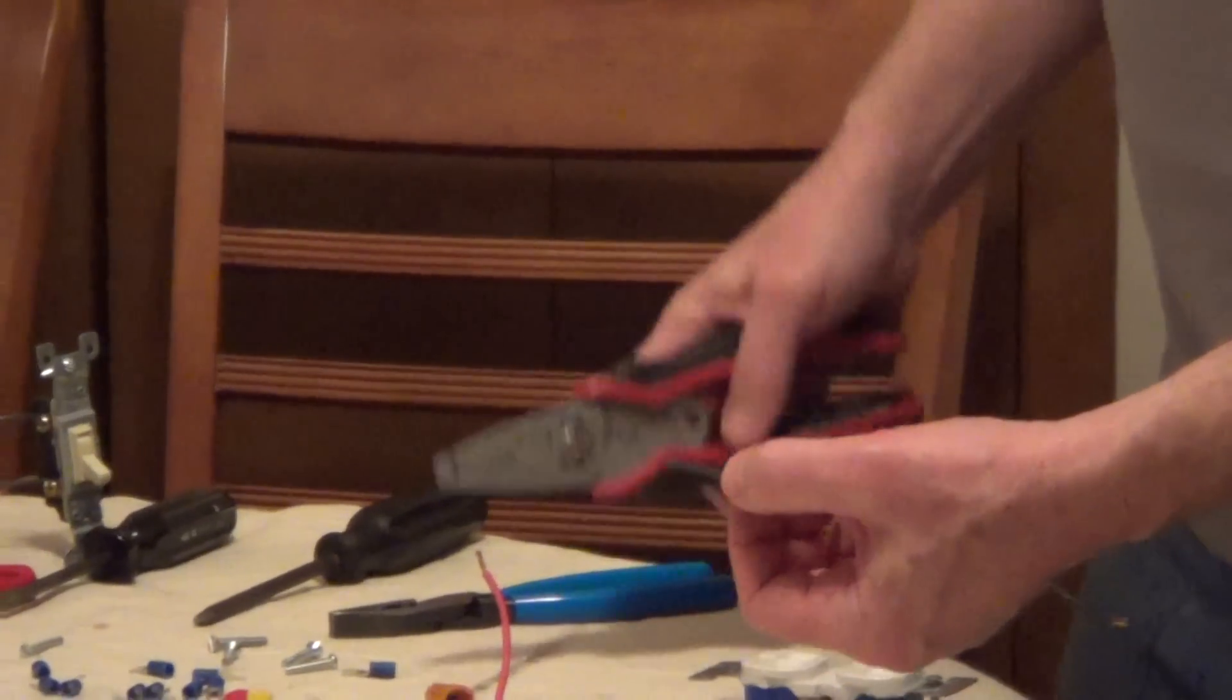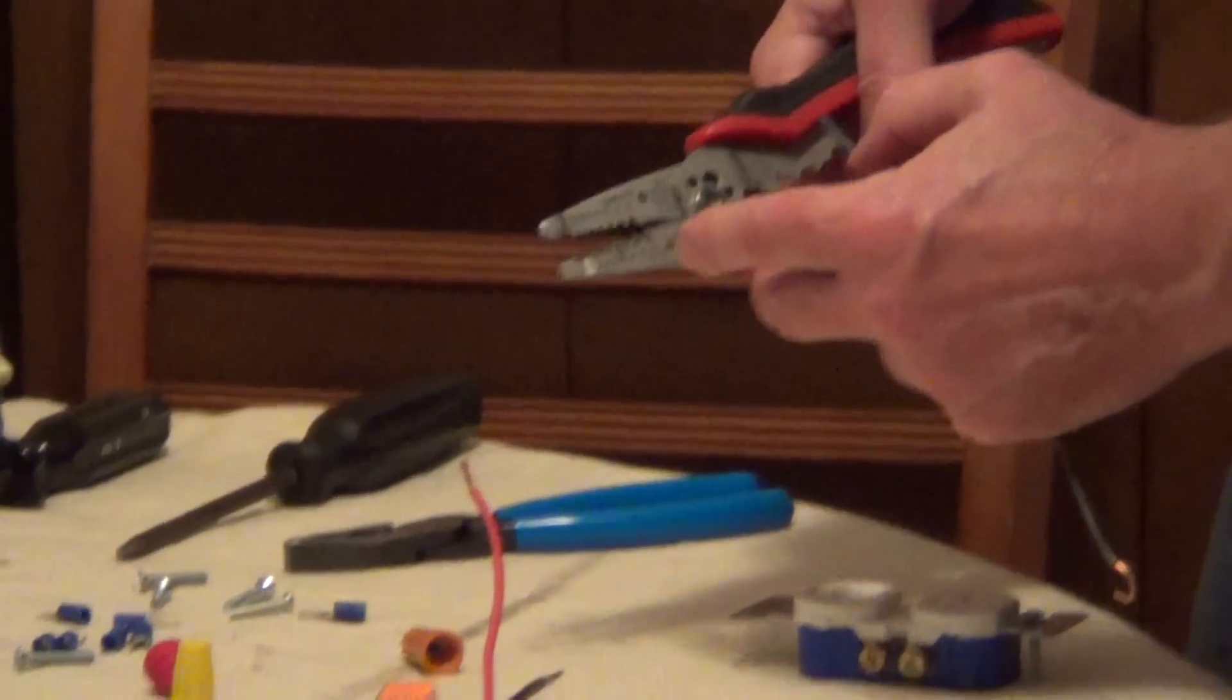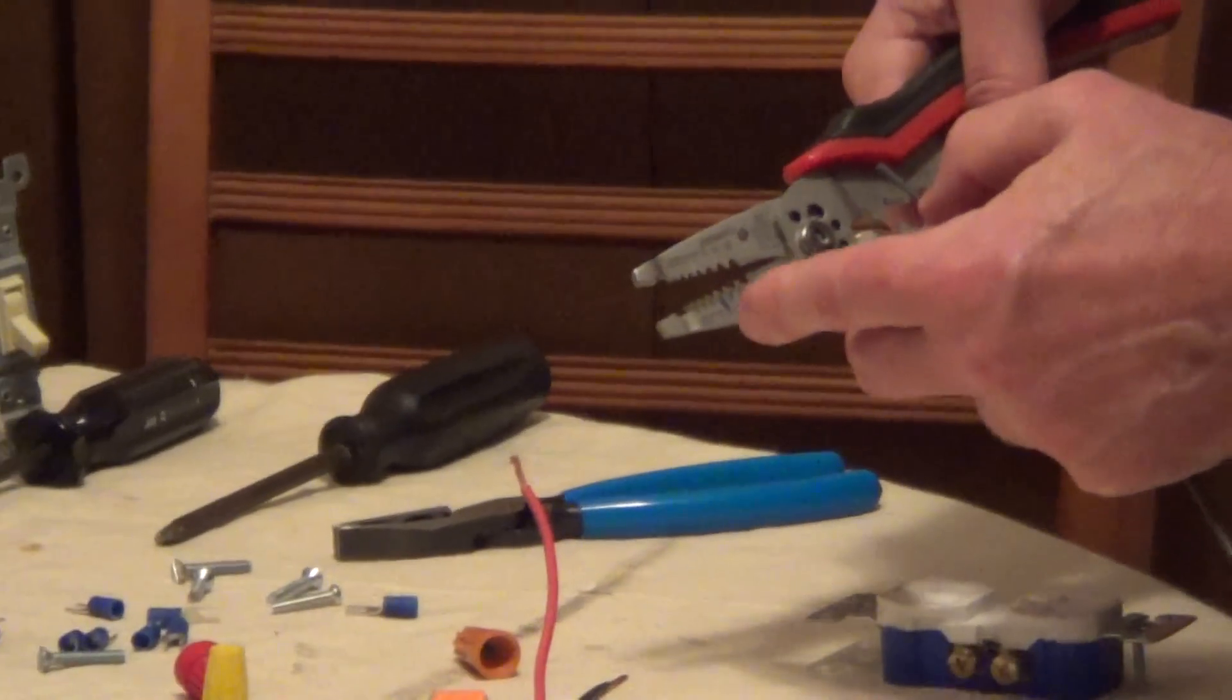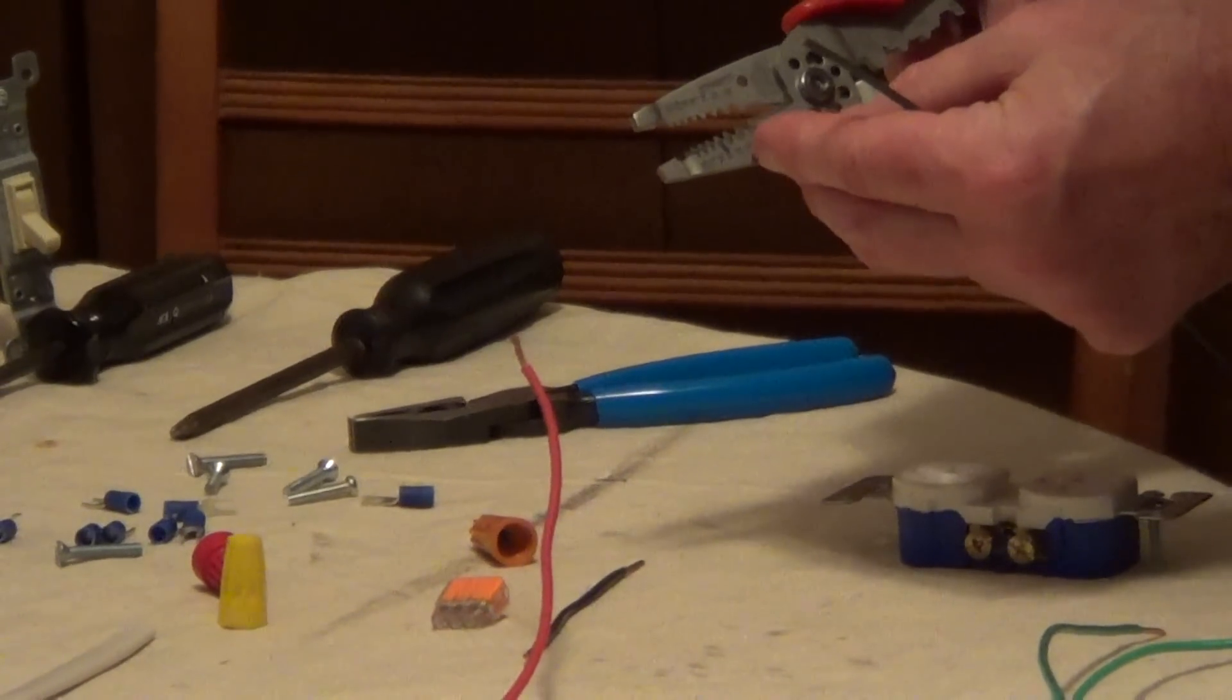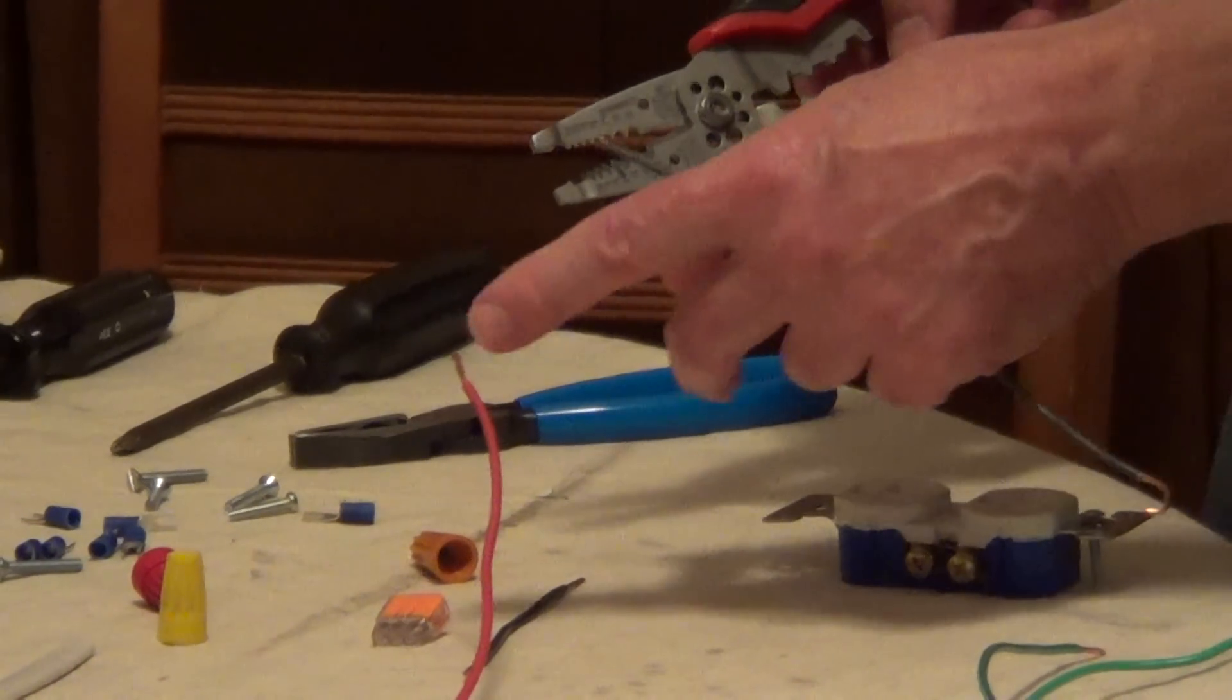So depending on what gauge you're using, for instance, this is 14 gauge, we would use the 14 notch to strip this. But if we were cutting the stranded wire, I would actually go up a notch to the 12 gauge and strip it so we don't cut into the wire.